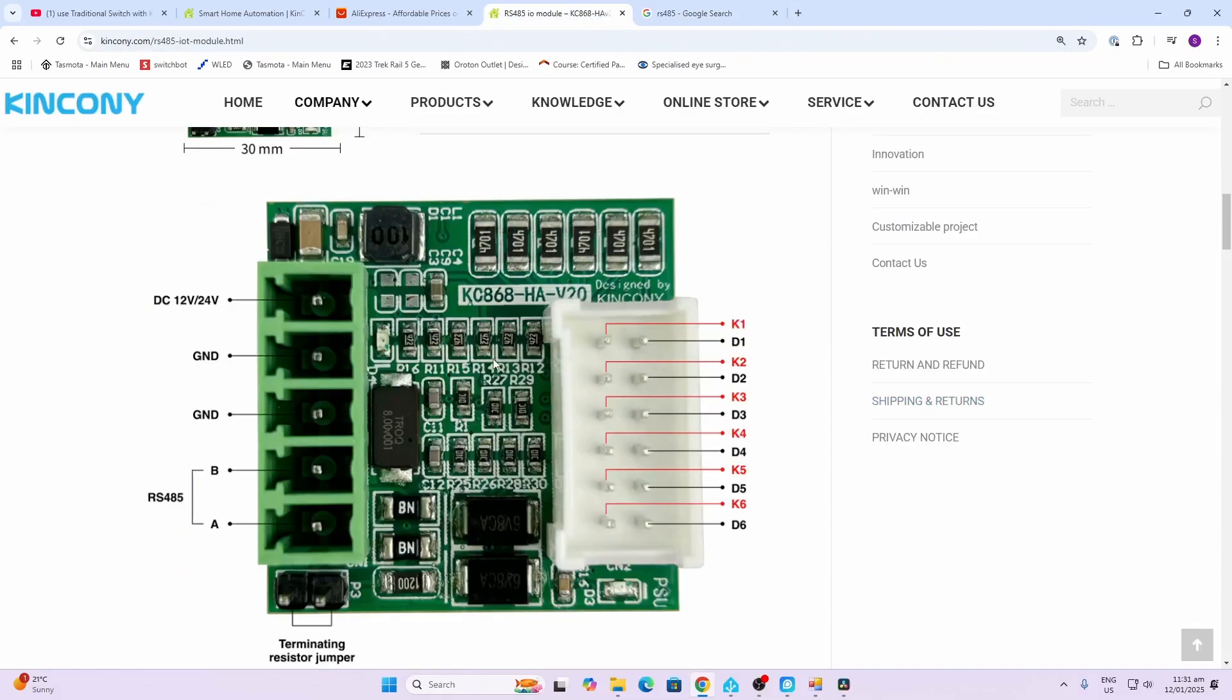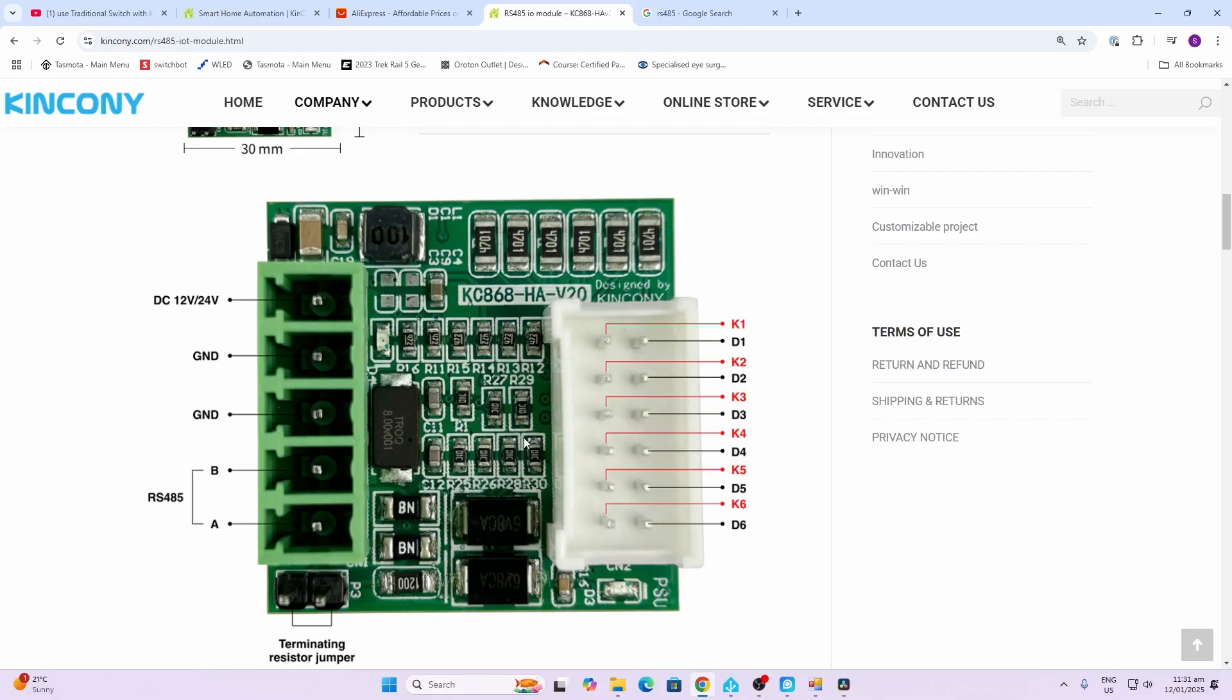Having a look on the other side of the device we have our inputs. These K lines are the inputs. We've got up to six individual switch inputs per unit and you would wire up the switch between the K1 and the ground post of the device as can be seen over here.